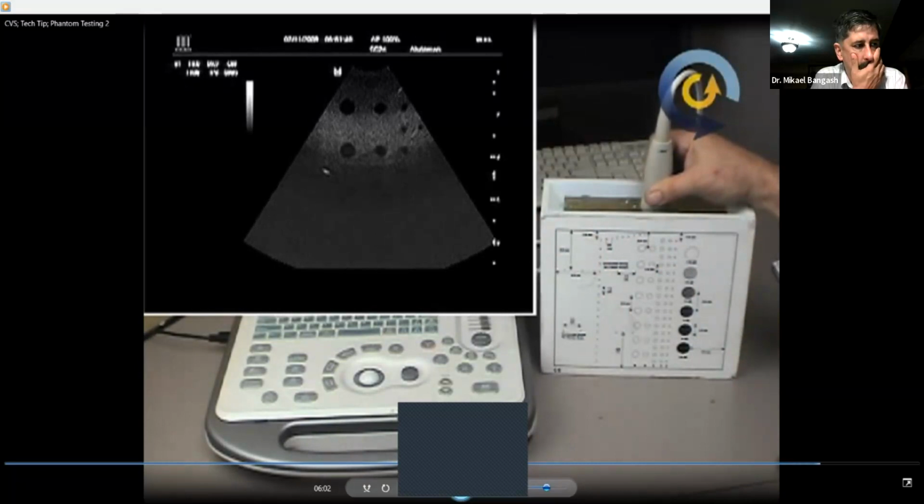Those are much more uncommon because they're very expensive, and they typically would just be in a good lab that had a reason to test that. Most of the Doppler verification is actually done electronically now, where it can inject a frequency and measure it back. So that's a use you're going to find of your transducer.